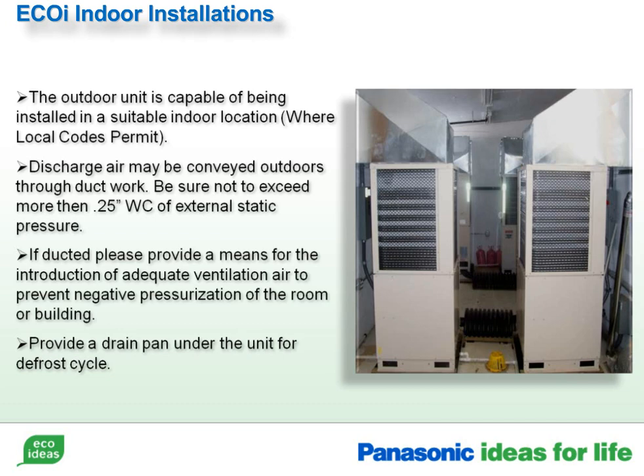Discharge air may be conveyed outdoors through duct work. Be sure not to exceed more than 0.25 inches of water column for external static pressure. If ducted, please provide a means for the introduction of adequate ventilation air to prevent negative pressurization of the room or building. Remember to provide a drain pan and drain lines under the unit for the defrost cycle.